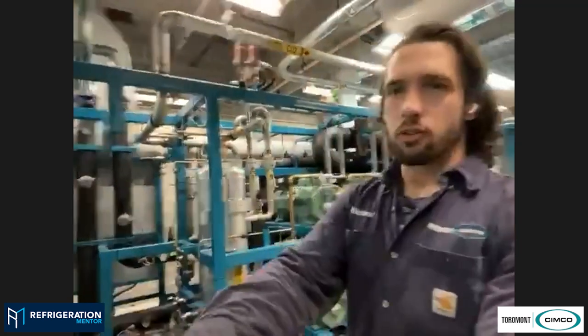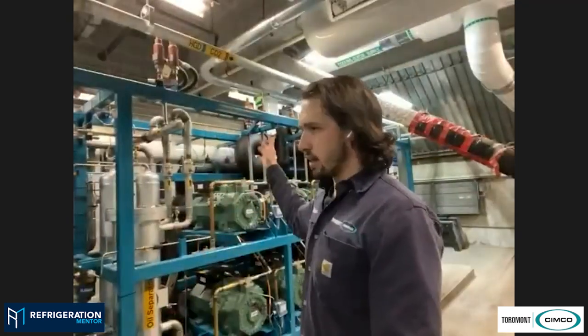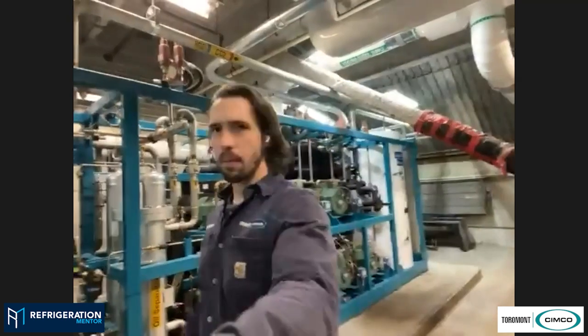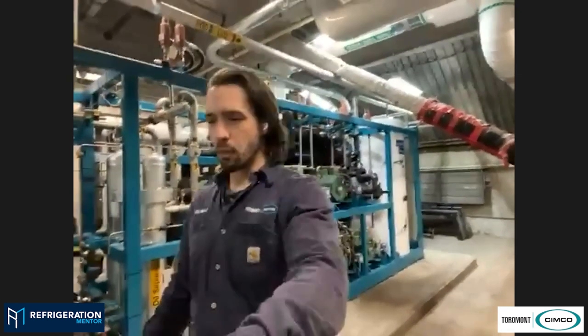Yeah, absolutely. Going forward, here's our discharge piping that goes up to our gas cooler. Here we have a Guntner adiabatic gas cooler. If it wasn't four flights of steps up, I'd take you up there to show you right now. But the CAG control system sends it an optimal outlet temperature based on various conditions. We send the signal to Guntner, and the Guntner controller generates its own algorithm which controls our target outlet temperature for our gas.